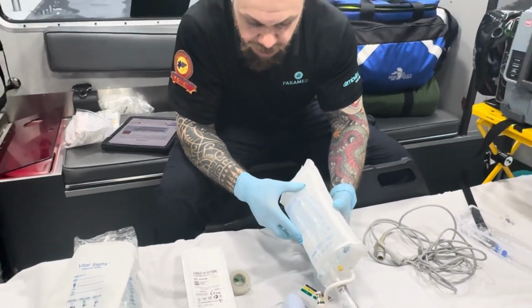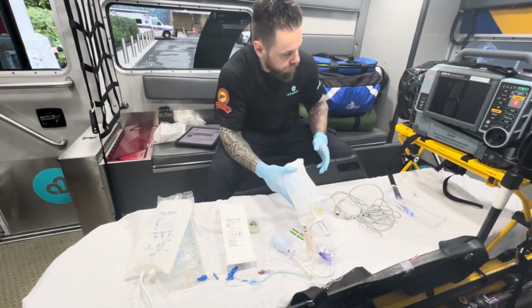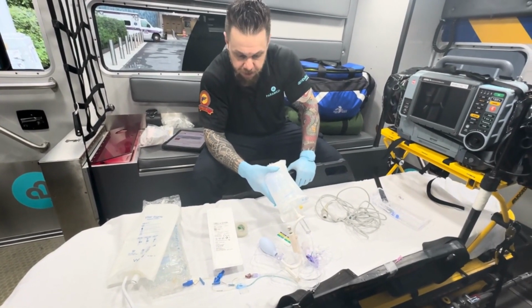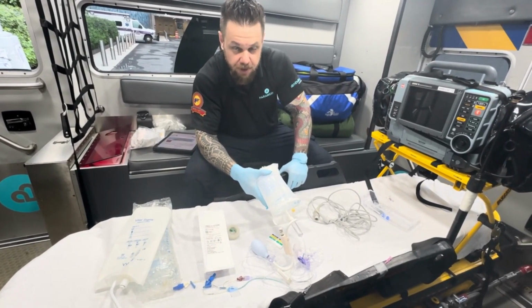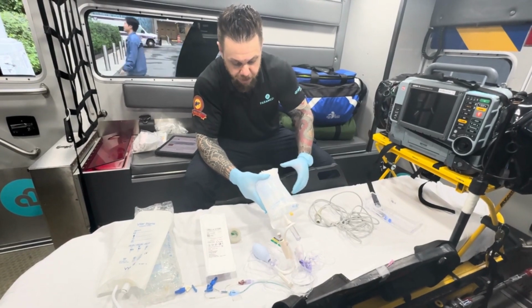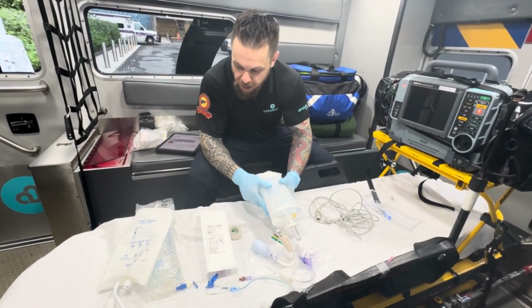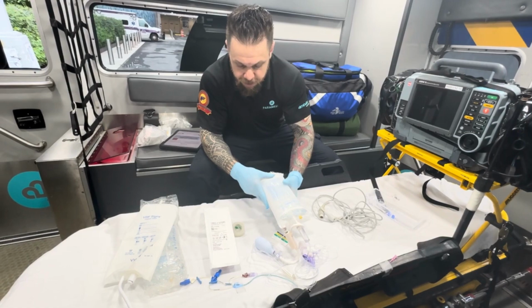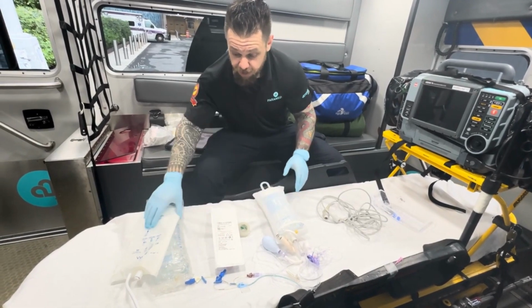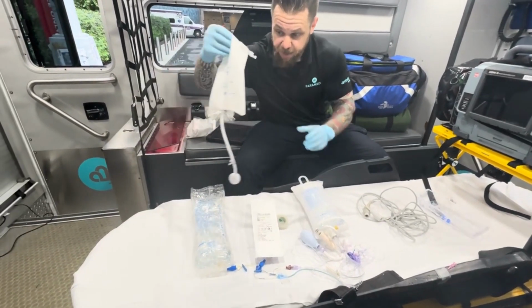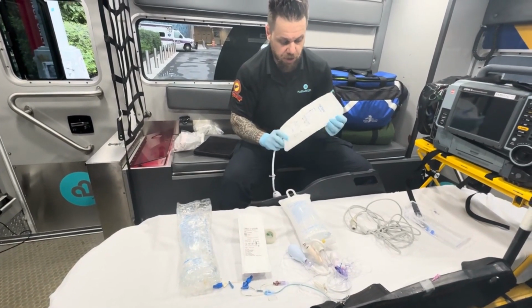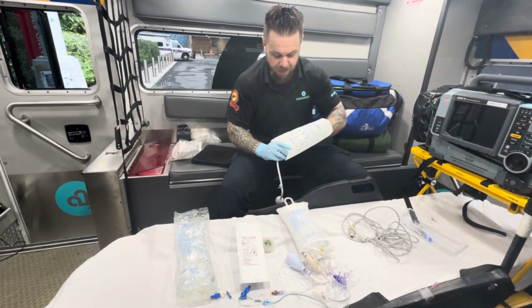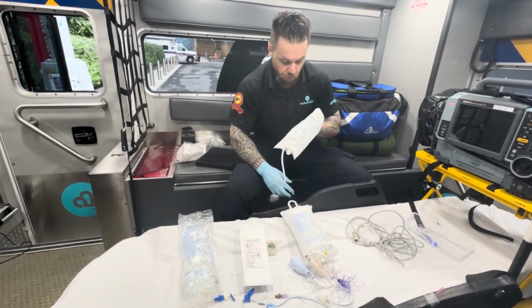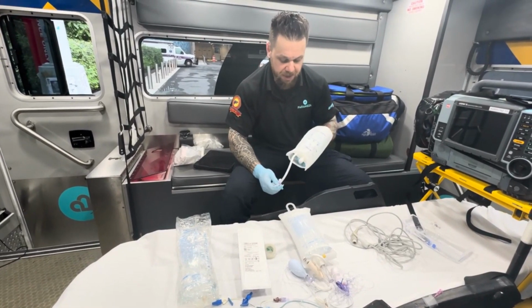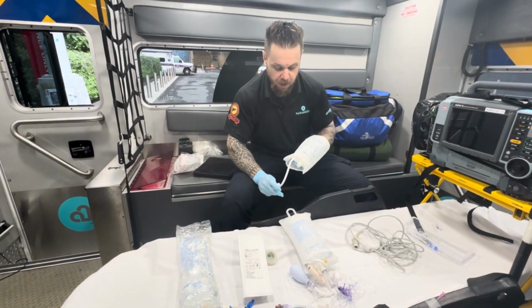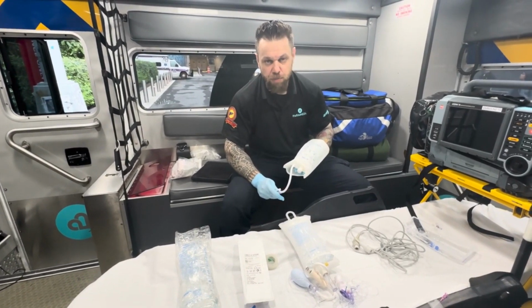So this transducer on this side is already set up. I already set this up because I wanted to show you how to do both the CVP and the arterial. The setup is going to be the same. So I already employed the 500 fluid here. I'm going to show you the 1,000. The concept is the same, but do not employ a 1,000 bag to fit this pressure cuff. Why? Because it's not made for 1,000, and if you do, you're going to either overpressurize it or underpressurize it, and you may not have the appropriate readings.